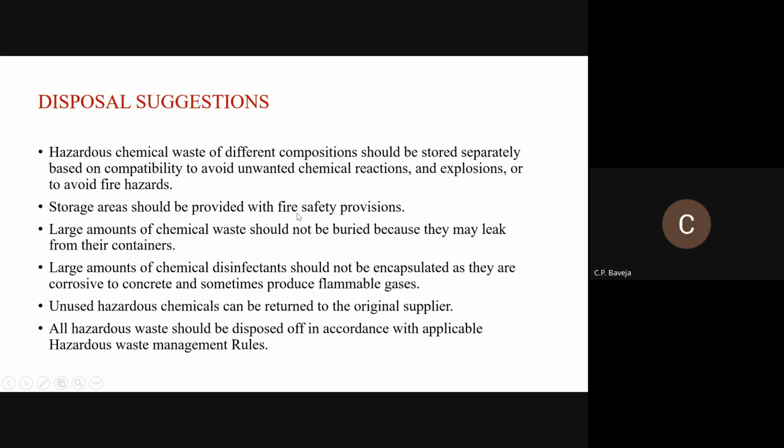The storage area should be provided with fire safety provision. If fire occurs, fire safety provision should be there. A large amount of chemical waste should not be buried because it may leak from the containers. And a large amount of chemical waste should not be encapsulated, as it is corrosive to concrete and sometimes produces flammable gases. Unused hazardous chemicals can be returned to the original supplier, and all hazardous waste should be disposed of in accordance with the applicable hazardous waste management rules.